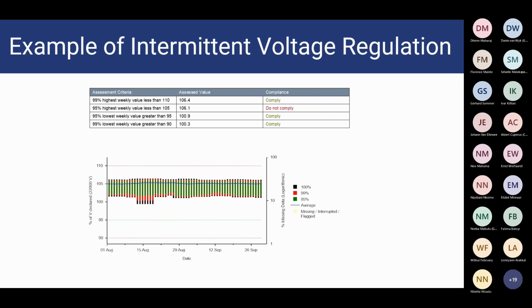All right, just to continue where we left off. This is just an example of the intermittent voltage regulation. What we can see here, at this specific point where we're measuring, is that the voltage regulation is quite stable, in a stable band, but the voltage regulation is high. So it's exceeding, on the upper value, the 105% limit for 95% of the time.